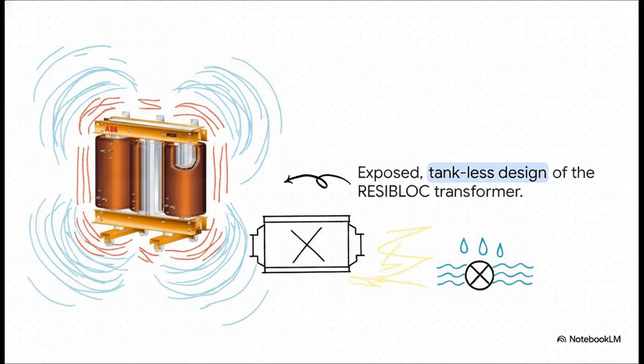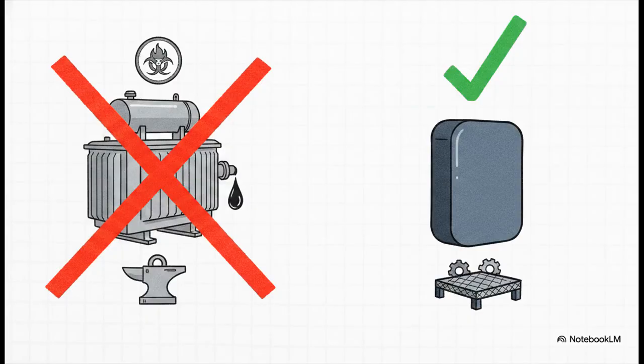That simplicity? That's entirely by design. Literally, no oil, no tank, just cast resin. Think about it. On an offshore rig, every square inch of deck space is heavily contested real estate. Hazards are quite literally everywhere. So introducing thousands of gallons of insulating oil into an enclosed space brings massive fire risks and huge weight penalties. By eliminating those insulating oils and those bulky containment tanks altogether, this level of mechanical simplicity becomes the core selling point. You get less infrastructure, way less risk, and significantly less maintenance for the crew.